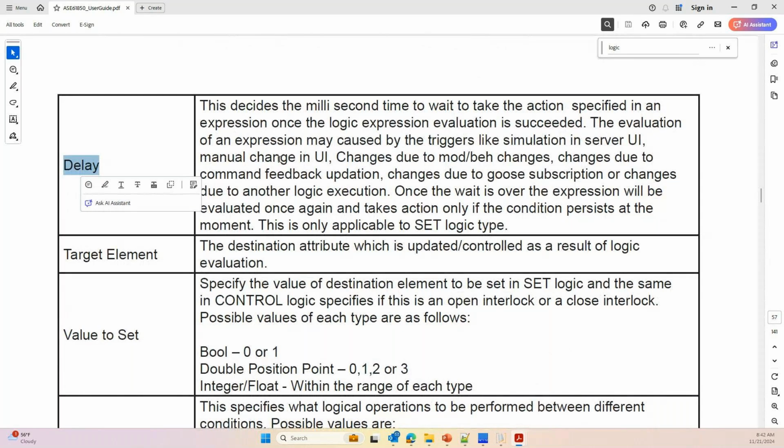We also have a capability to introduce a delay in the action. So that means if you are interested to set a delay, instead of doing it instantaneously, you may introduce a delay and do the same action. This will allow you to assess the situation or condition multiple times. So initially when the condition is met, it will trigger the activation, or it will arm the action, but it will actually perform the action only after the delay.